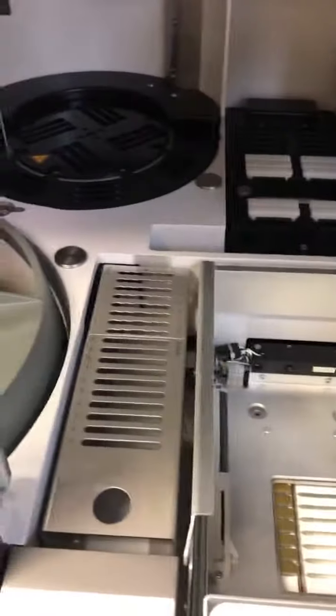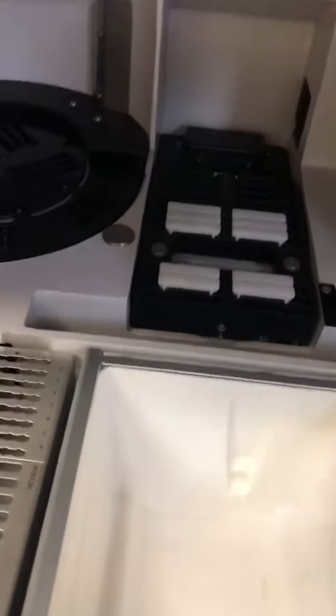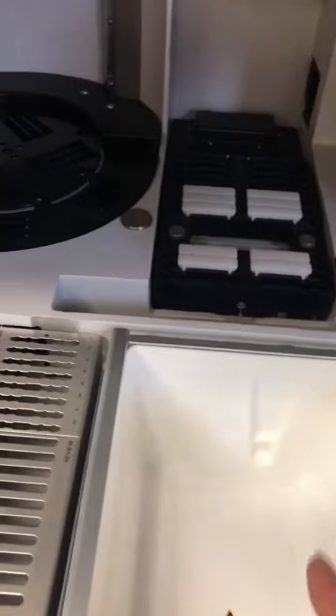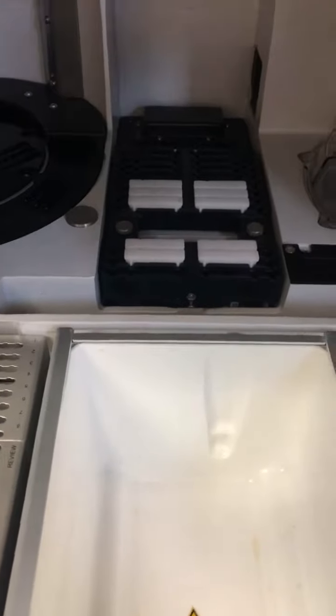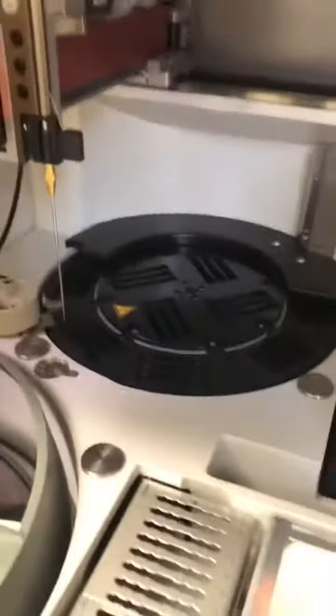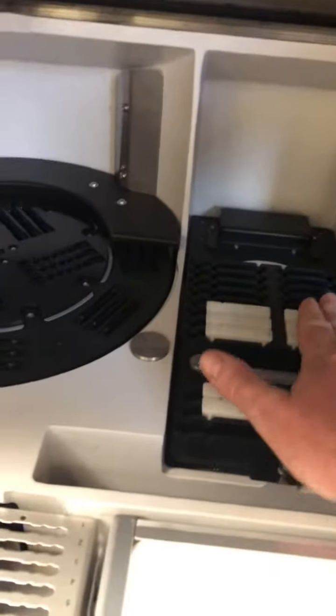we empty our waste cassettes. And the reason we empty the waste cassettes is because when we reinitialize, the instrument does not know what the count is in the waste basket. So we're happy with everything. We've checked our pipette, we've cleaned our position, our card puncher is pointed in the correct direction, we have removed any obstructions here that might be on the gripper arm, our centrifuges are all clear, and we're ready to do our restart.